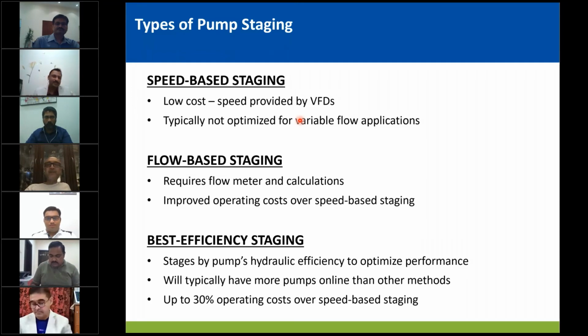That's the speed-based staging. Flow-based staging is more efficient, best practice, but it needs a flow meter, which is expensive to have in each line or each pump. Or if you have it in the main header, then you will need a bigger flow meter, and it becomes more expensive as well. So often we don't see this flow-based staging due to this challenge, but smart pumps can provide flow from their controller. So this is another opportunity that you might have going by flow-based staging.